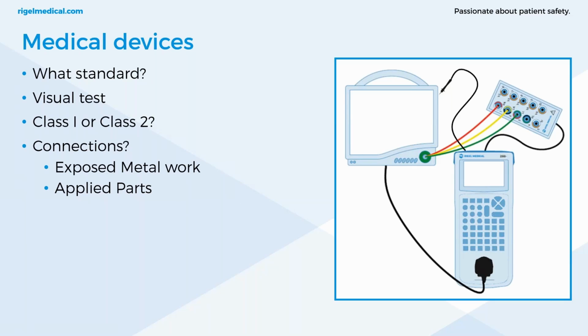So what standard are you using first when you're testing a medical device? Well, in this webinar today, we're talking about NFPA 99, but in some cases you might be using a type test standard like IEC 60601, or an alternative recurrent testing standard to NFPA 99 like 62353. What else is included? A visual test that highlights most of the issues you're going to get with a medical device. So that's housing defects, cabling, does it have the correct fuse rating, just looking at the device as a whole. Is the instrument class 1 or class 2? What connections does it have? Does it have any exposed metal work? Are there applied parts?